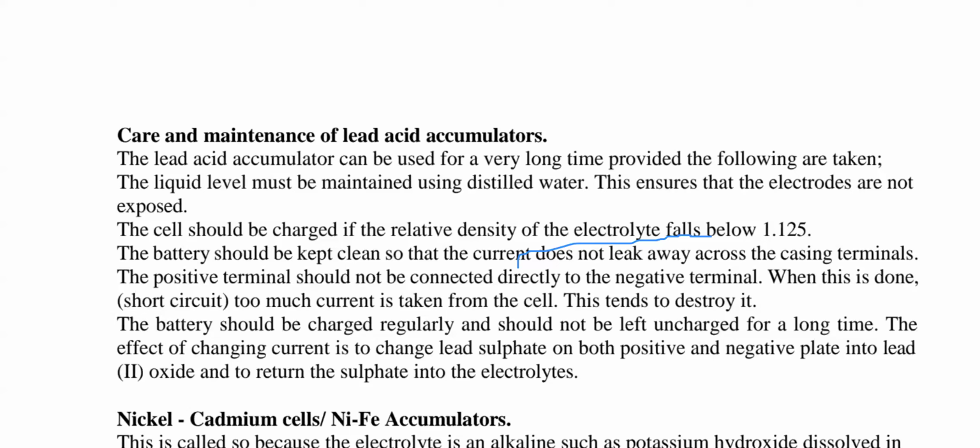Then again, what you should know is that the cell should be charged when the relative density of the electrolyte falls below 1.125. That's when you're supposed to take the battery to charge. You don't just go and charge it.